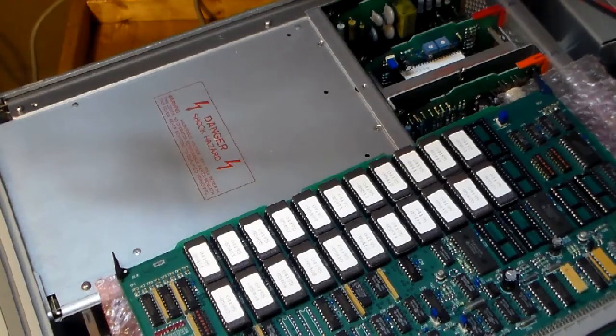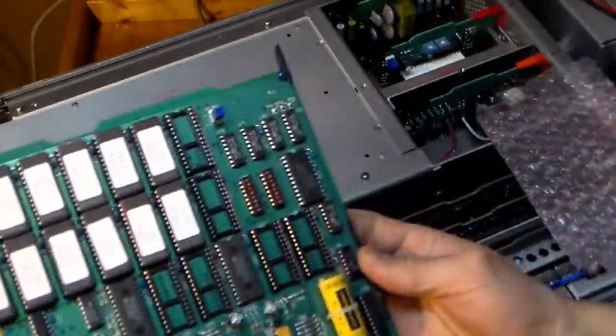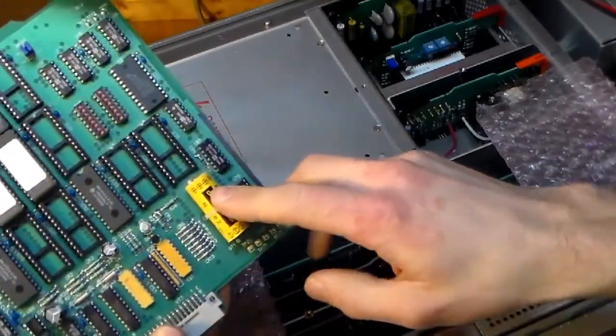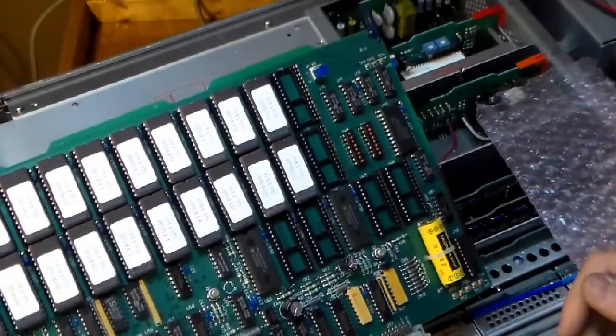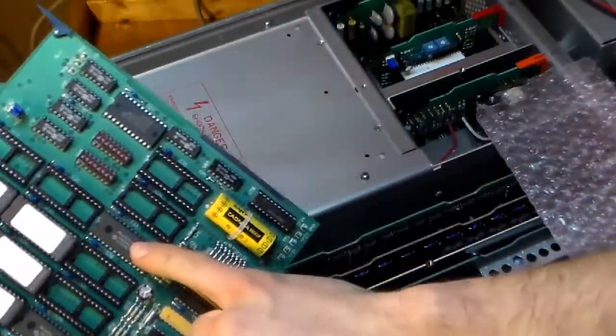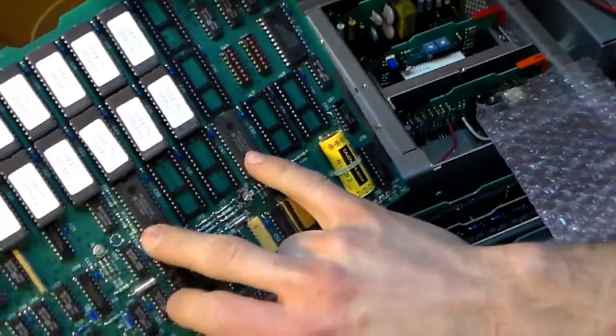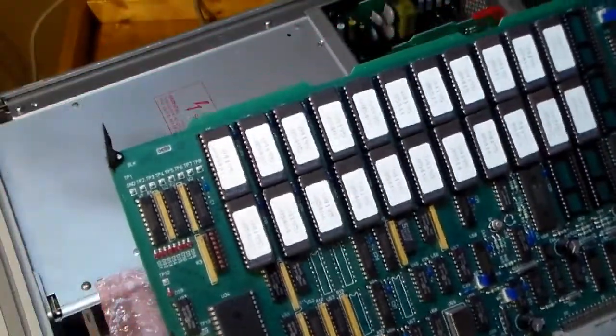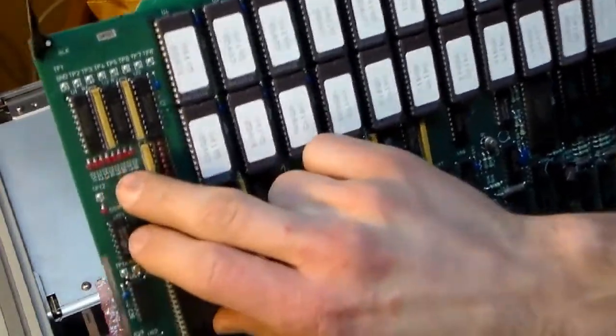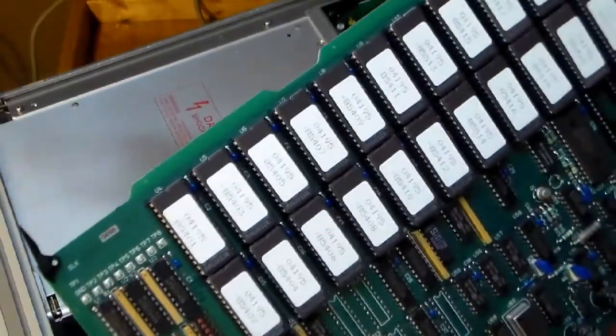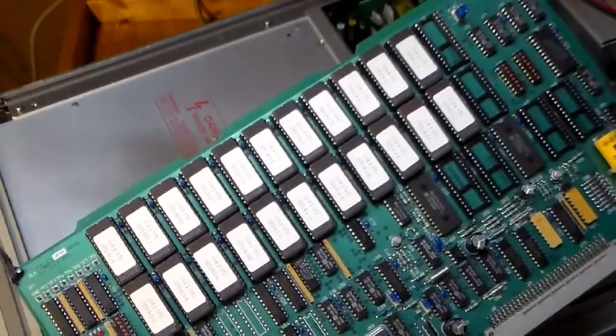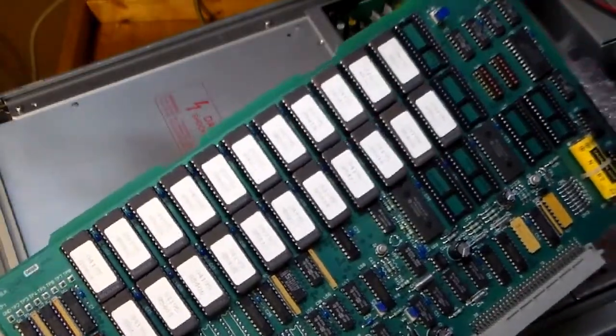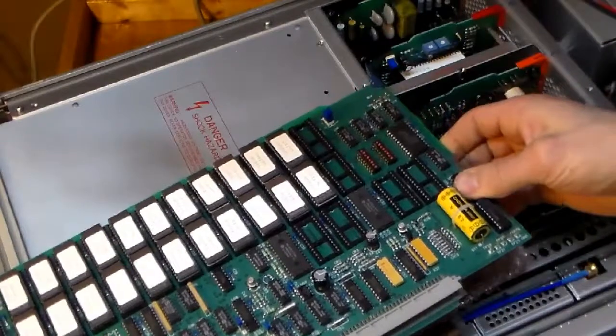So in order to check the battery backup RAM, I took out the A6 board. So the battery's right over here, I'll check it in a moment. And the rest of the board just has a bunch of, I think those are ROMs, and these are the two RAM ICs. And when the unit was on, I didn't pay attention, but there's a bunch of Diagnostics LEDs right over here. And I don't think any of them turned on, which sort of indicates no reset or no clock or something seriously wrong or just nothing happening.